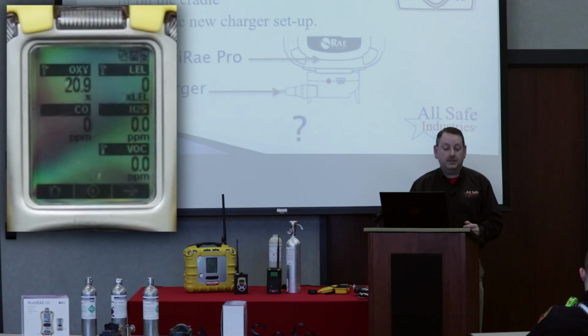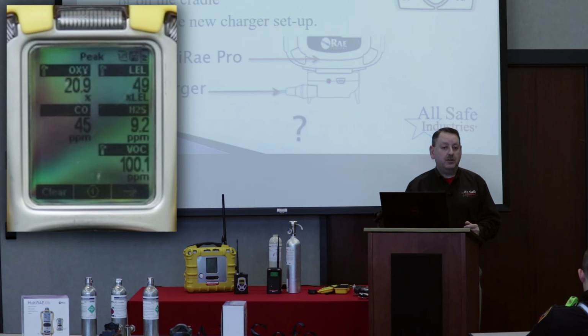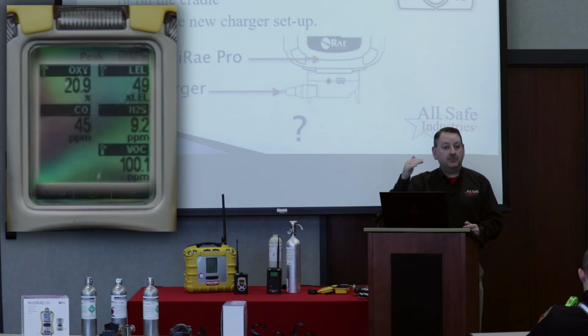So everybody hit the no button to select that right arrow. And the next page of information on your MultiRAE, what's it say at the top? Peak. So what peak means, it's the highest reading since you've had the instrument turned on. And so whatever the highest reading for each channel will be displayed on the peak page.